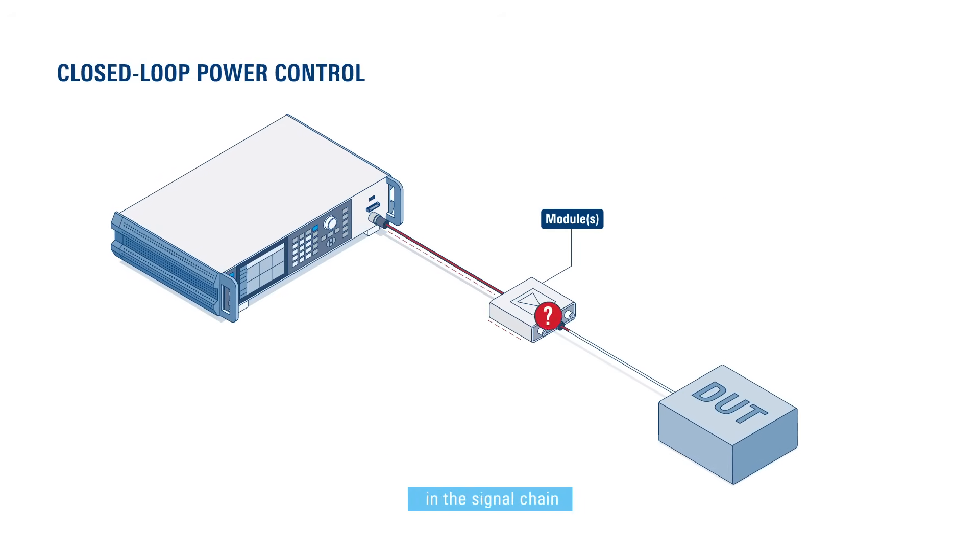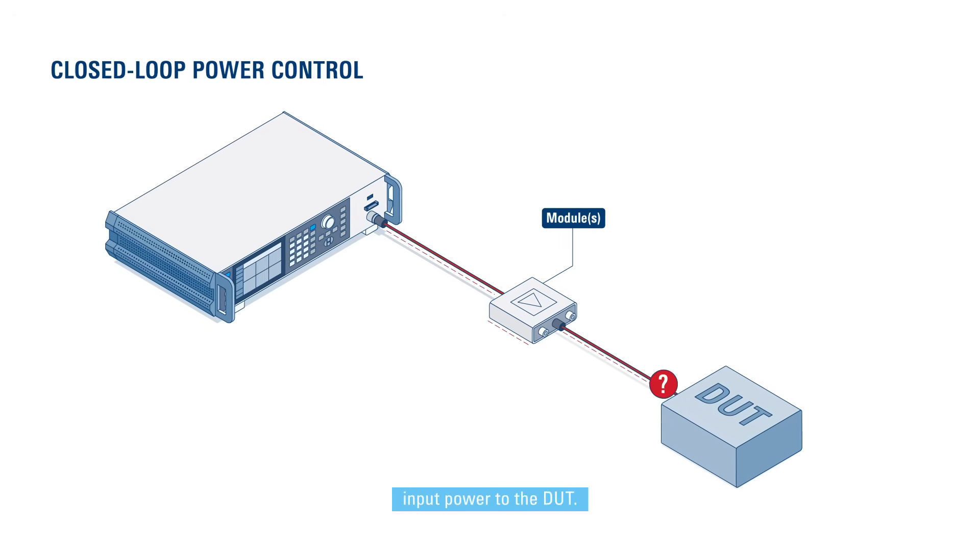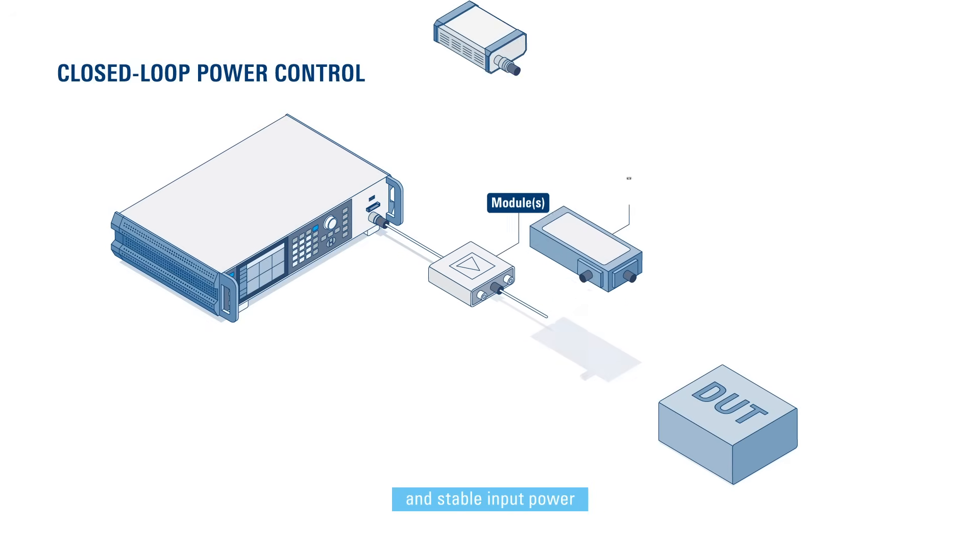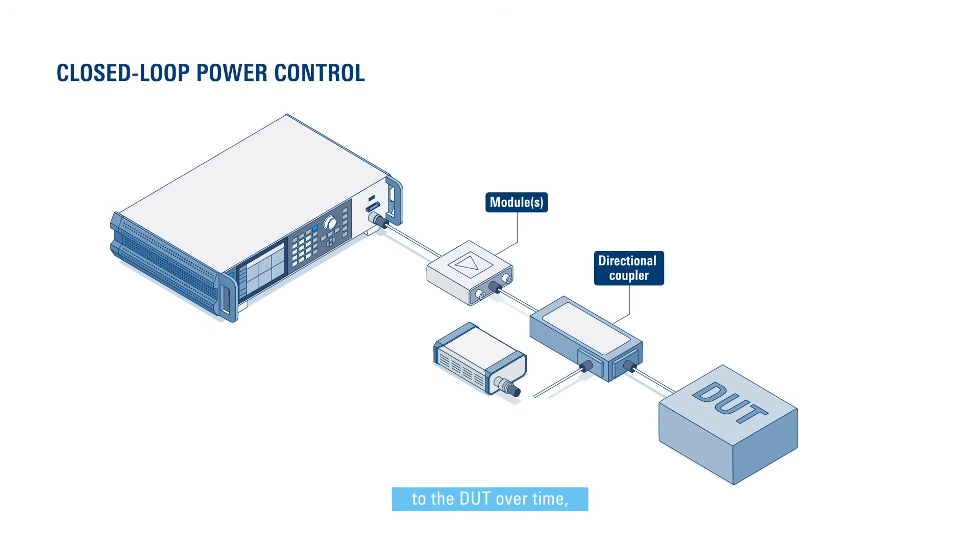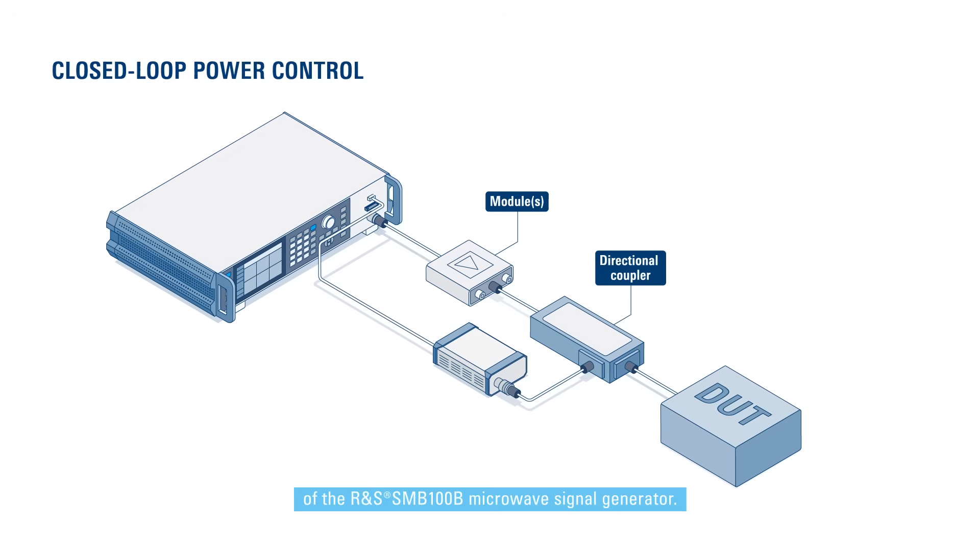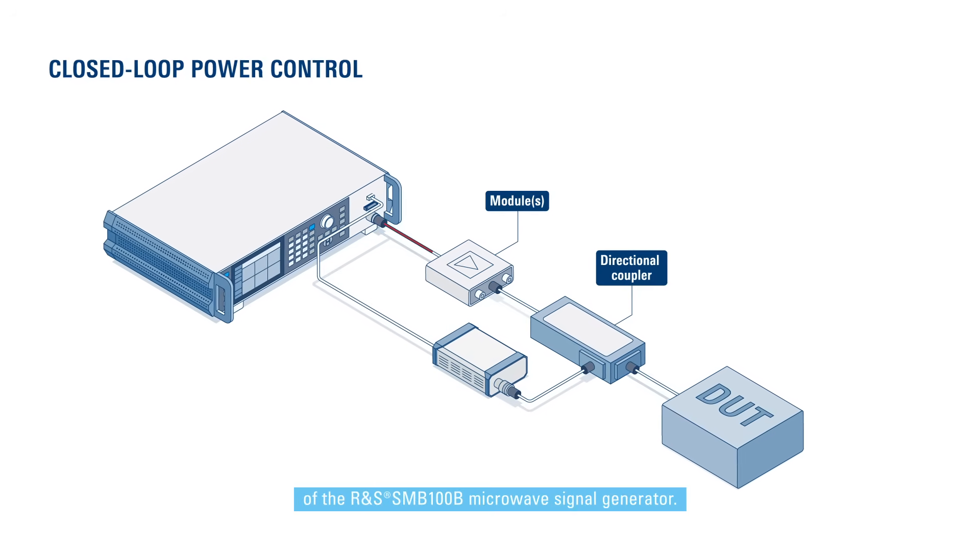Unexpected losses or gains in the signal chain can result in unknown input power to the DUT. To ensure a highly accurate and stable input power to the DUT over time, we've made dynamic closed-loop power control a standard feature of the SMB100B Microwave Signal Generator.